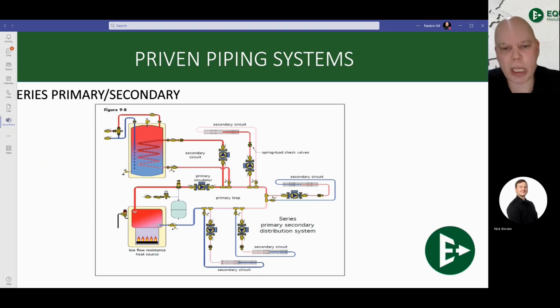So you will see, as we come out of the system, we have the same problems with this system as we had with our original series system, where if all of the zones are calling, you get colder and colder as you go on. Now, that's not going to happen all the time. Sometimes only one of these secondary circuits is calling, or maybe only the last secondary circuit, and you need to design it in a way that it can see vast fluctuations in supply temperature and still not overheat the zone.